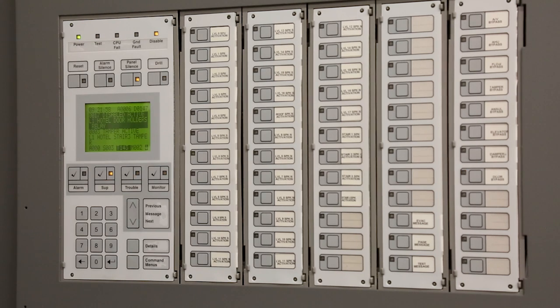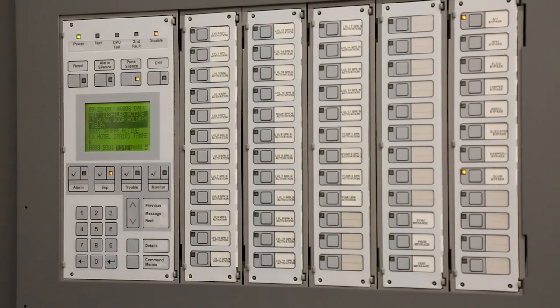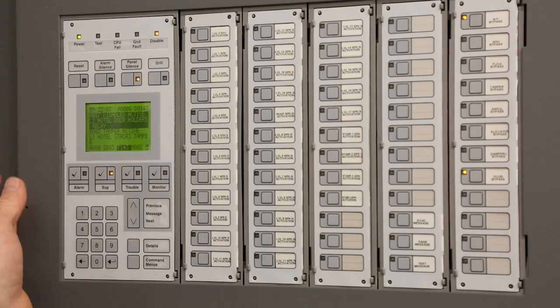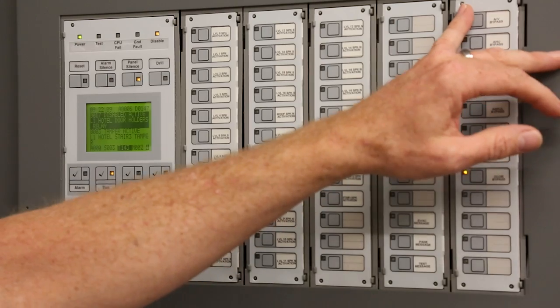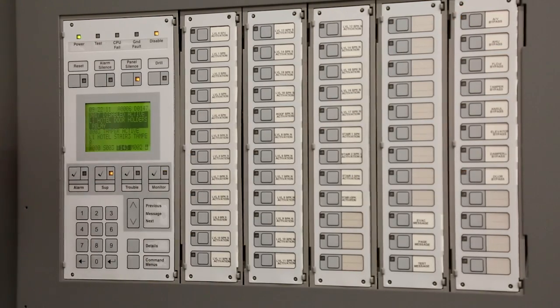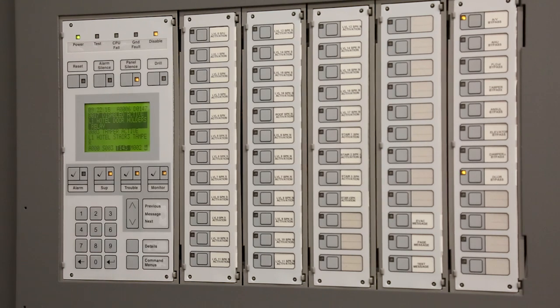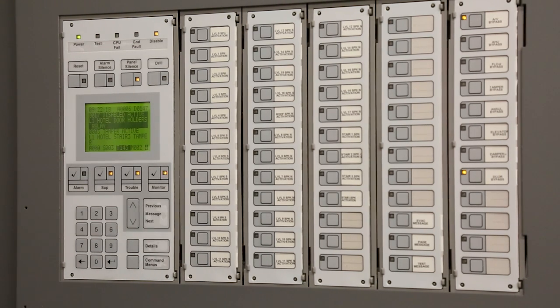I will say one thing though, if you are in alarm, do not bypass when you're in alarm. There will be a problem, okay? Only bypass when the panel is out of alarm. For instance, if you bypass the AVs in alarm and you go to reset, they're going to be re-triggering again because you're trying to tell it to stay out and then you're doing it again.